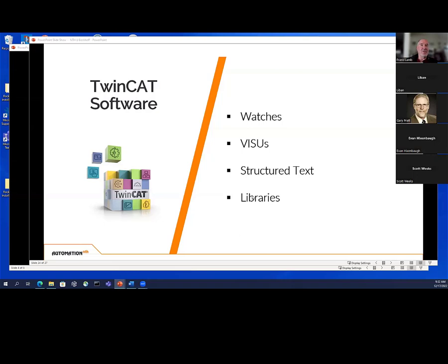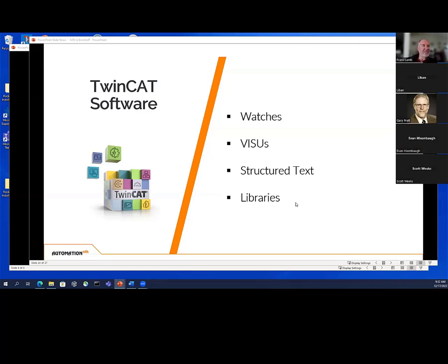The best way to do it is to simply use the newest firmware — everything should work if you use the newest stuff. But when you go back and use remote manager, you could have all kinds of mismatched libraries. Fortunately, one thing I got out of it was every library that the tech support guy had — every single version — so I could swap things out myself. It was numeric entry only on my visualization that was the problem.